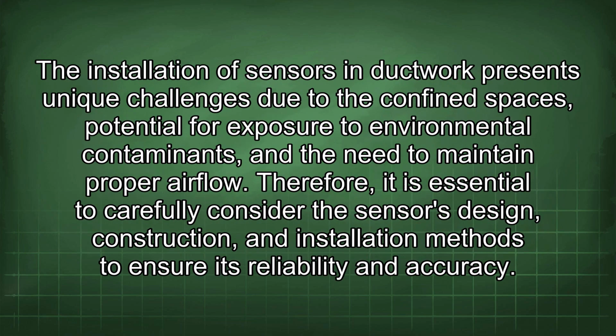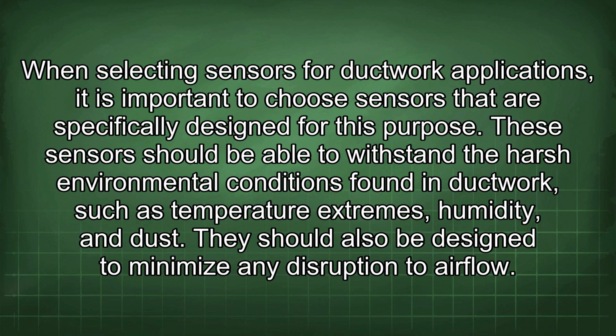The installation of sensors in ductwork presents unique challenges due to the confined spaces, potential for exposure to environmental contaminants, and the need to maintain proper airflow. Therefore, it is essential to carefully consider the sensor's design, construction, and installation methods to ensure its reliability and accuracy. When selecting sensors for ductwork applications, it is important to choose sensors that are specifically designed for this purpose. These sensors should be able to withstand the harsh environmental conditions found in ductwork, such as temperature extremes, humidity, and dust. They should also be designed to minimize any disruption to airflow.